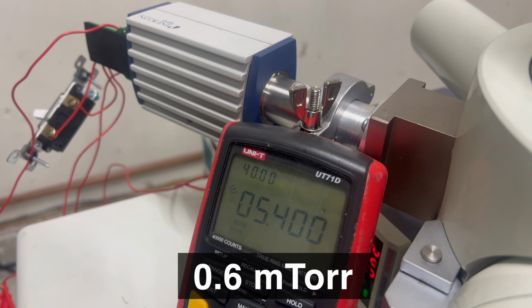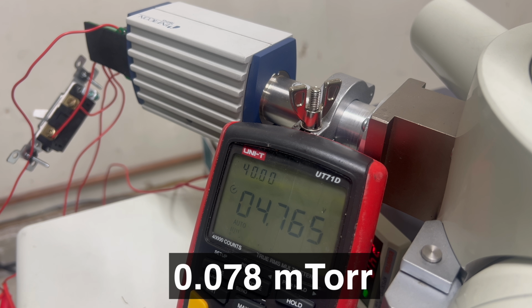I was certain that I'd have to replace the oil in the diffusion pump, but it looks like the pump is operating just fine. After a couple of minutes, it reached a pressure of about 1 times 10 to the negative 4 millitorr, which is about 500 times lower than what it was in the pre-evac mode. This is well into the high vacuum region, and is an acceptable pressure for running the machine. Awesome! Now that the vacuum system is working, it's time to see if the machine is functional.